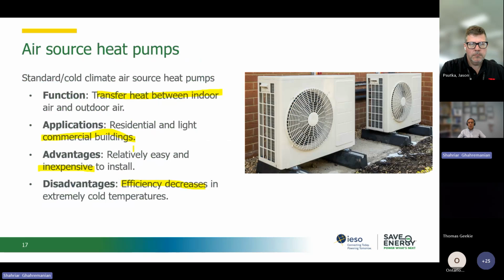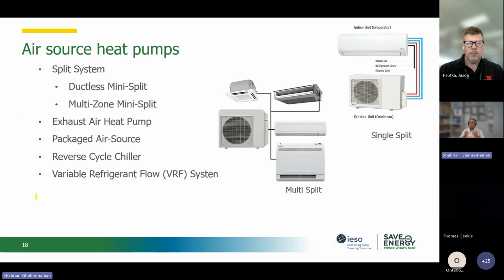The only disadvantage is that the efficiency of the standard one decreases with extremely cold temperatures, and that's when we sometimes need to shut down the air source heat pump and run a backup system, because a standard heat pump cannot bring the heat from outside to inside. But with a cold climate air source heat pump, there is no worry and no need to consider supplemental heat. Typically with a standard air source heat pump, what I saw is that when the outdoor temperature reaches -6 to -10 degrees Celsius, that's a good time to turn it off and use an auxiliary heating system. So the air source heat pumps are like this. We have a split system. The split system can be ductless, which means that we have refrigerant lines going from the outdoor unit to an indoor unit.